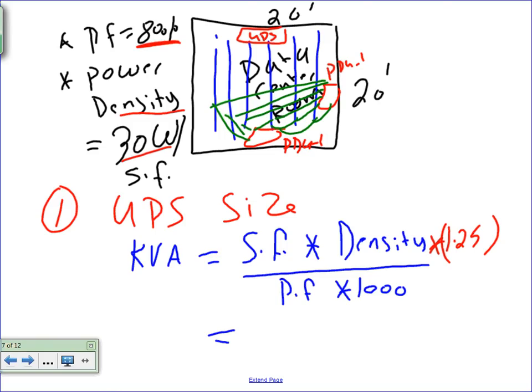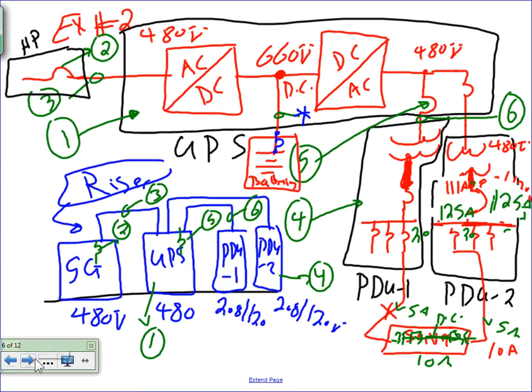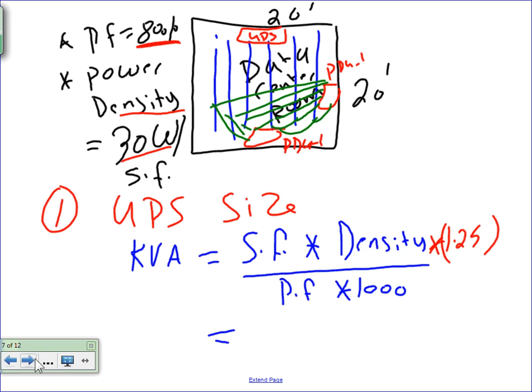So how do we size this? We size it based on the square foot of the building. So let's go ahead and start sizing. The first thing we need to do is, did we have a PDU? Okay. So we have our PDUs. Let's start sizing. I need somebody to help me with this. So 20 by 20. Where does the 20 by 20 come from? Square foot of the computer room.